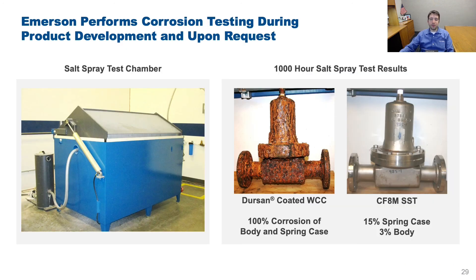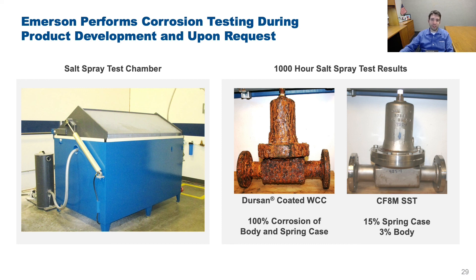To close, I'll highlight two areas where Emerson can help mitigate corrosion risks. First, we can perform corrosion testing in our McKinney lab upon request. Using our salt spray test chamber, we tested the Fisher MR95 pressure regulator — commonly used in oil and gas applications. On the left is a WCC steel unit with a coating; on the right is the same unit in CF8M stainless steel. After 1,000 hours of salt spray testing, the photos speak for themselves to illustrate how important material selection is in corrosive environments.